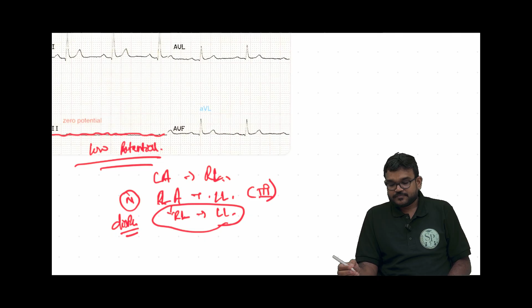One important point to highlight here: if the left leg is reversed with the right leg, then what will happen? See, the left limb is a normal lead, where the potential difference is recorded between the left arm and left leg and right arm and left leg. So if the left leg is reversed with the right leg, usually there is no significant change in ECG, and you cannot identify the lead reversal between the left leg and right leg.